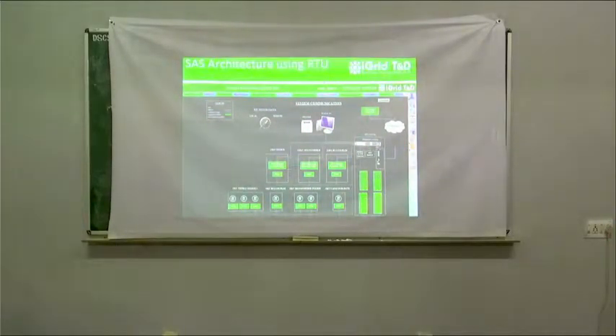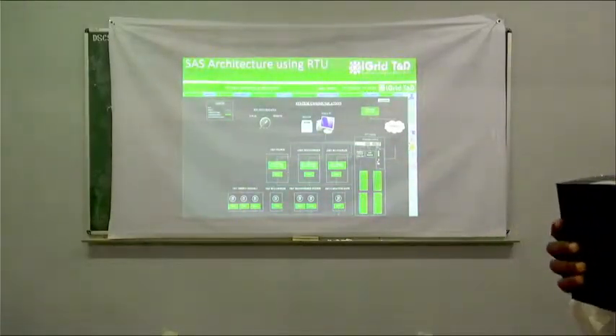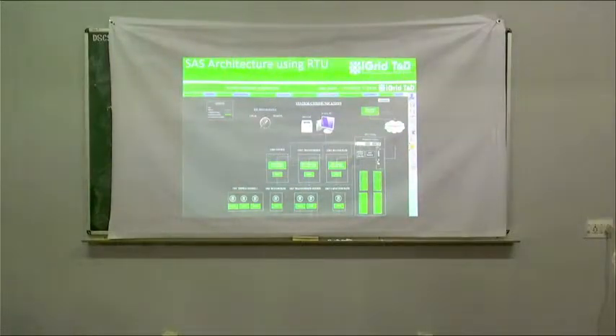Now, say for example, there are legacy substations, old substations. For the new substations, they always give a specification that they require a bay control unit, that is with HMI, where they can control the operation through a bay control unit. We can also do it using an RTU. The RTU is nothing but this one. That is the BCU, whereas this is the RTU. Again, there are different types, like digital inputs and digital outputs. This is an RTU.